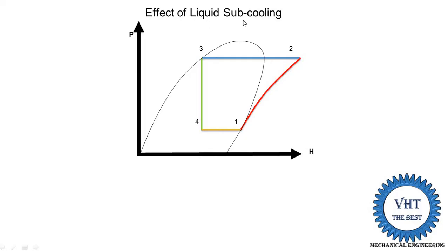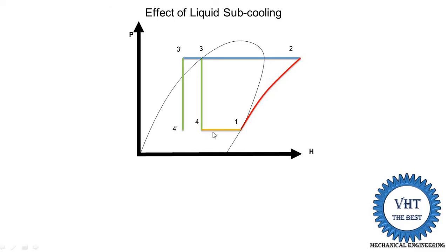The first factor is the effect of liquid subcooling. Subcooling means reducing the temperature of the liquid refrigerant coming out from the condenser at point 3, the outlet of the condenser. After point 3, we further reduce the temperature of the liquid refrigerant using a subcooler or by increasing the water flow rate into the condenser. When we reduce this temperature, the heat rejection line is extended further, giving us point 3-dash, followed by the expansion process at point 4-dash, and the refrigerating effect line is increased from 4-dash to 1.